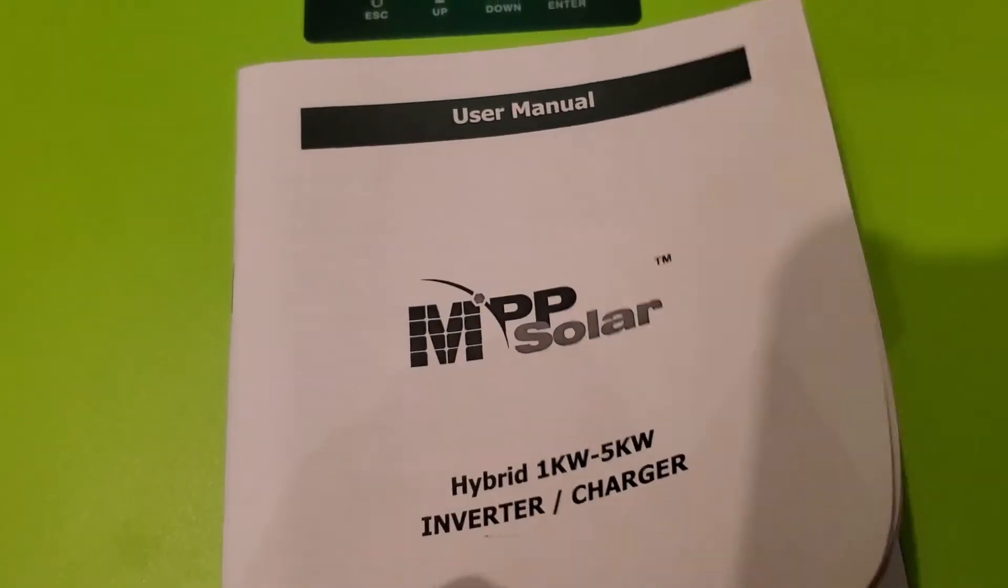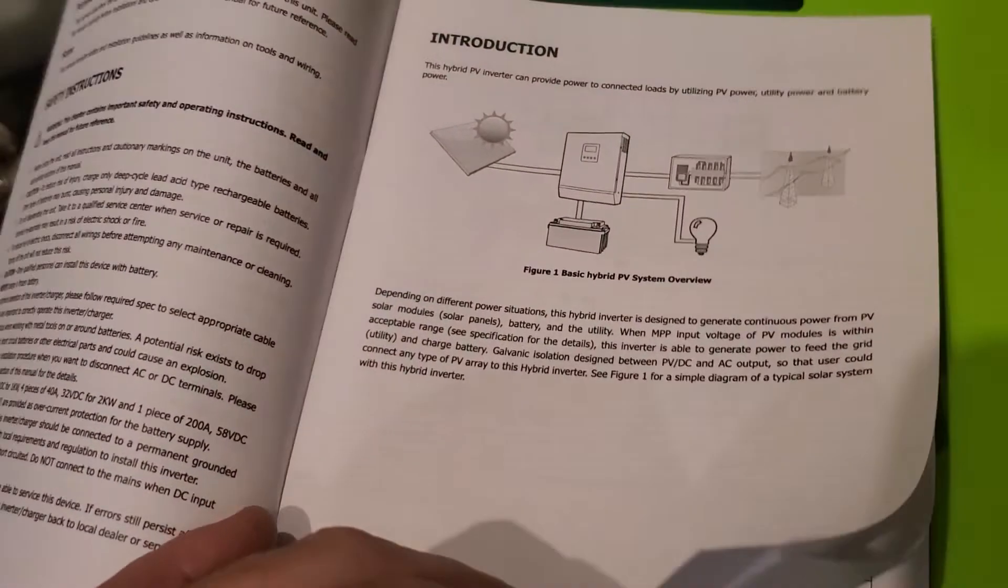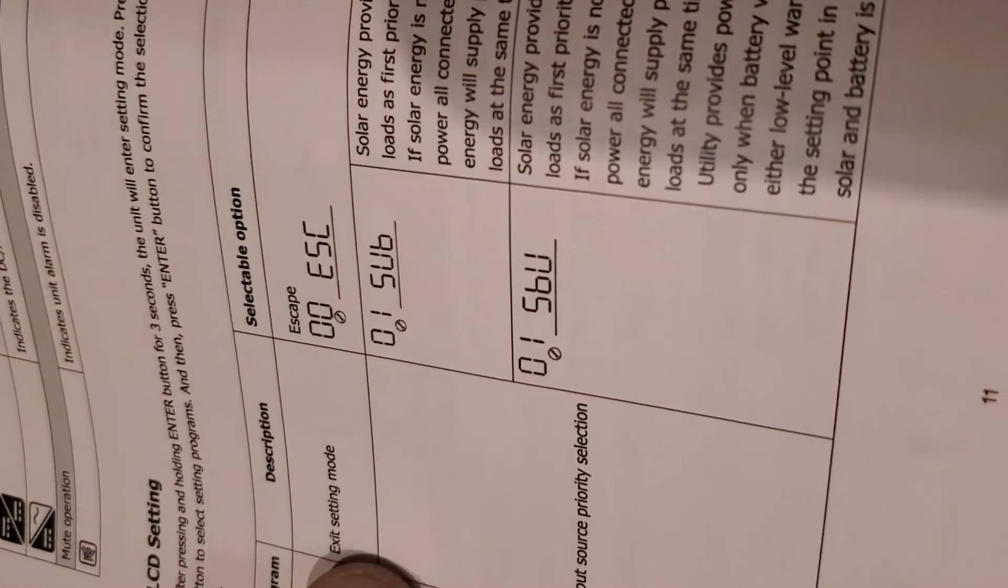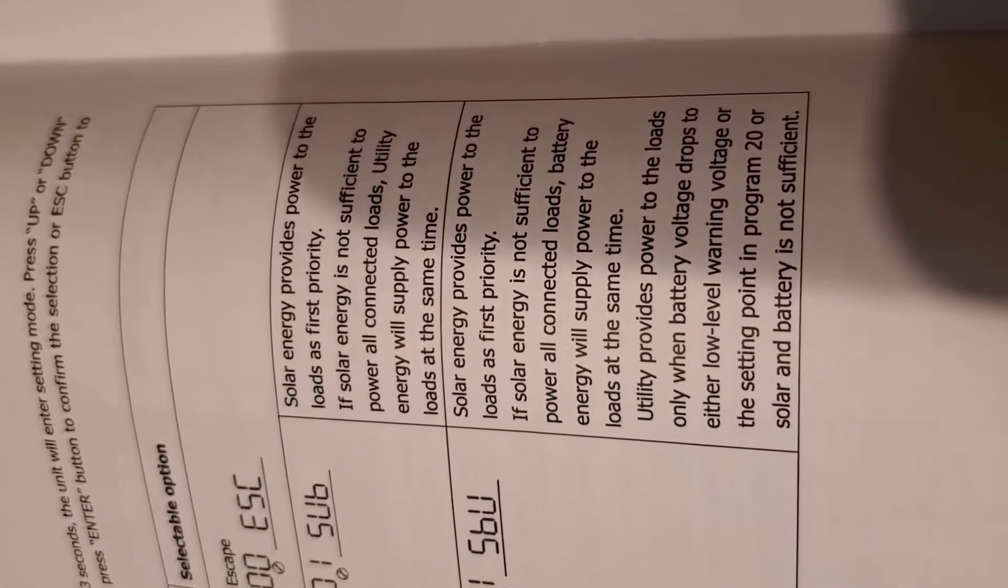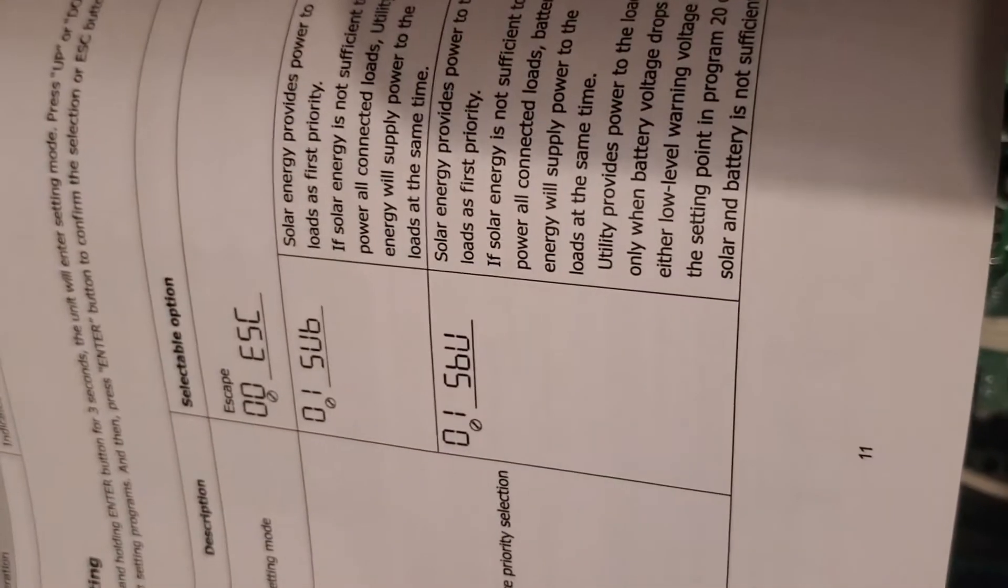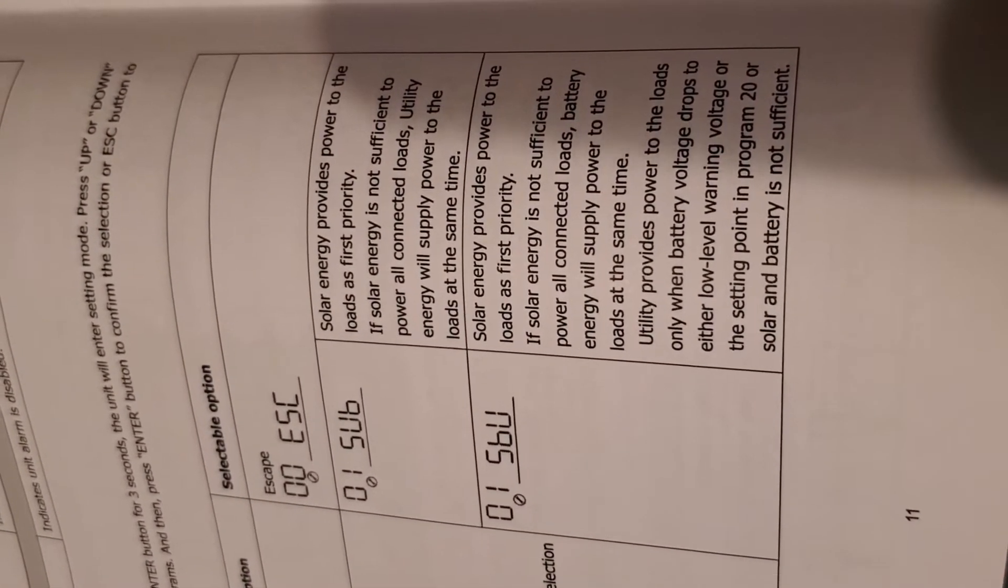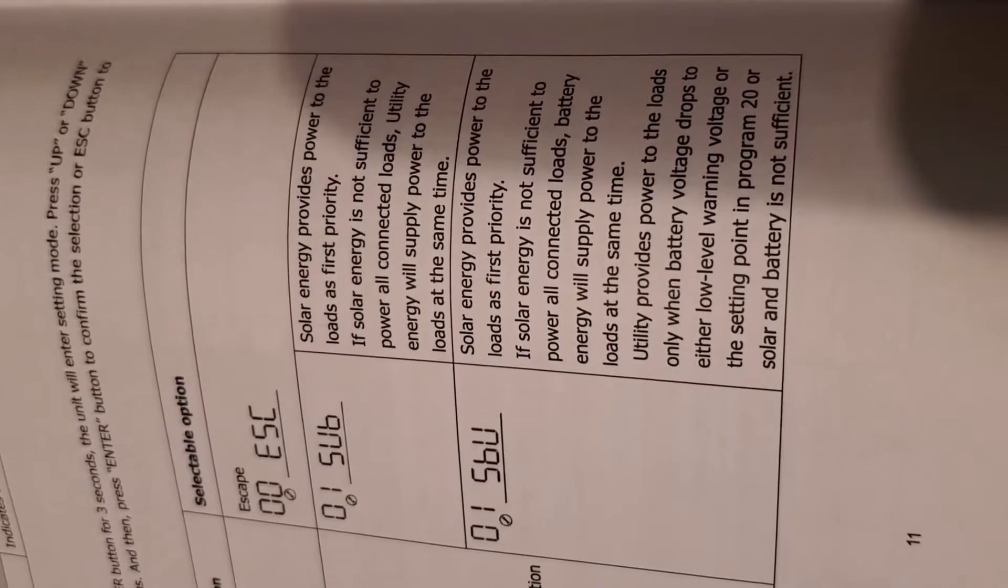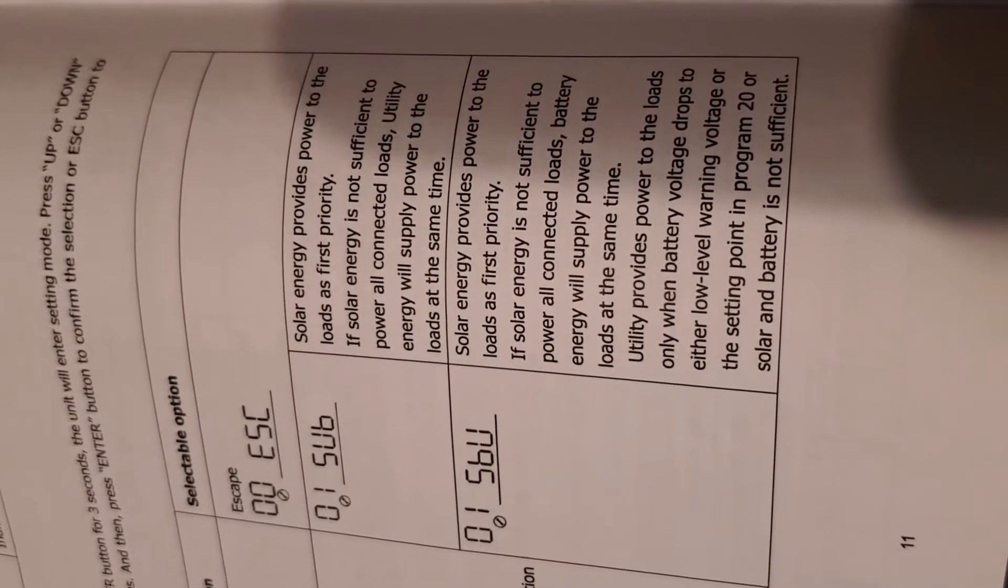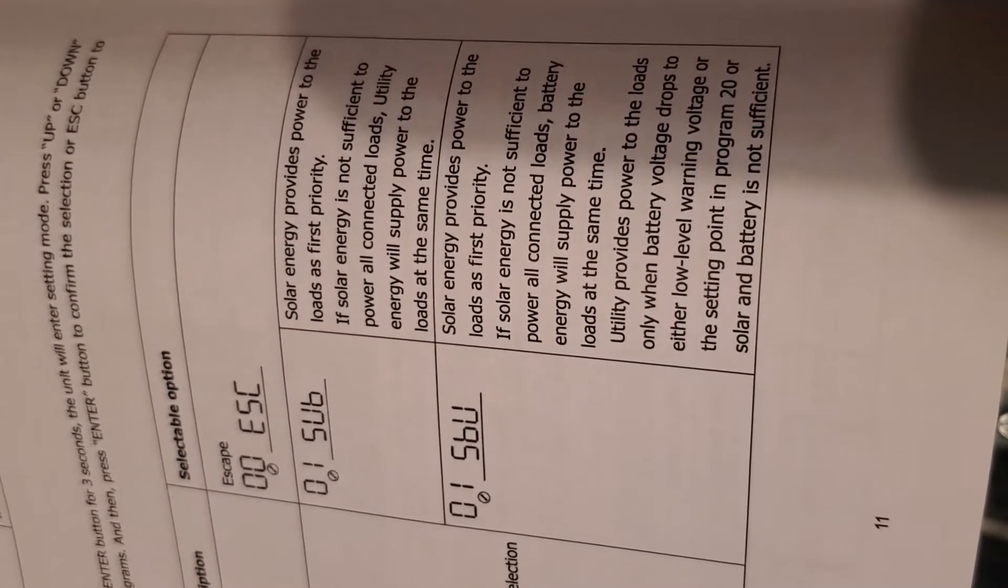I'm not sure what it is, so let me see if I can find the manual. Let's see if the guy actually used the manual. So I'm gonna walk you guys through everything that you would want to do on this. On the first part where I showed you that SUB, that's solar energy provides power to the load as first priority. If solar is not sufficient to power all connected loads, utility energy will supply the power to the loads at the same time. SBU is solar energy provides power to the load as first priority. If solar energy is not sufficient to power all connected loads, battery energy will supply power to the loads at the same time. Utility power provides power to the loads only when the battery voltage drops to either low level warning voltage or the setting point in program 20, or solar battery is not sufficient.